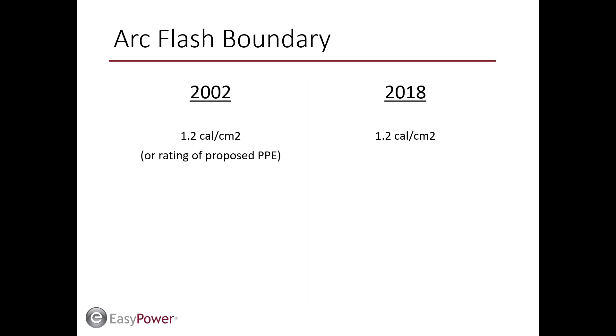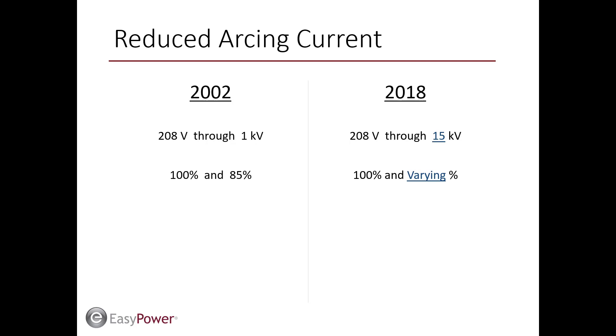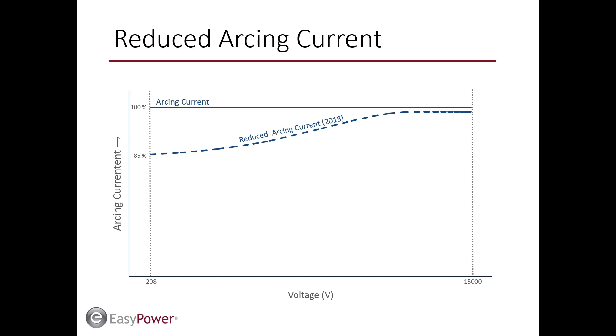Arc flash boundary: incident energy at the arc flash boundary is now fixed at 1.2 calories per centimeter squared. Language from the previous standard indicating an alternate incident energy at the arc flash boundary could be used is now removed. The new guide retains methods to consider reduced arcing currents and their ability to increase arc duration. The variation is revised from a fixed 85% to one that varies based on voltage, with less reduction at higher voltage levels. Previously limited to low voltage equipment, the new arcing current variation correction factor is now applied throughout the entire voltage range.